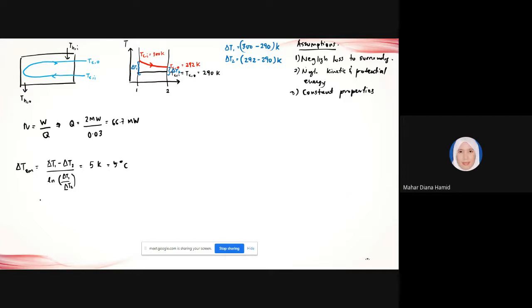After that, we need to get the value of A. If you remember, for a shell and tube exchanger, Q equals U times A times F, where F is the correction factor of the shell and tube, times delta LMTD. In order for us to get F, we need to refer to the previous graph.